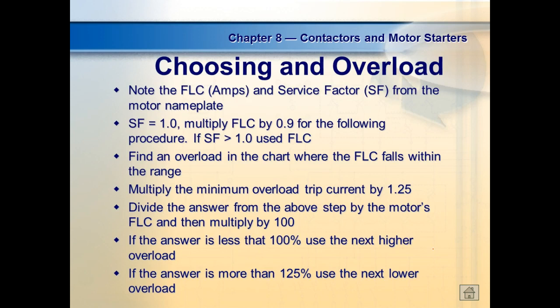Find the overload in the chart. Right off the bat, with a service factor of one, I would multiply it by 0.9. If it doesn't have a service factor of one, if it's got something greater, then I just use the full load current, whatever's on the nameplate. Then I'm going to find that current within a range inside that table over there.